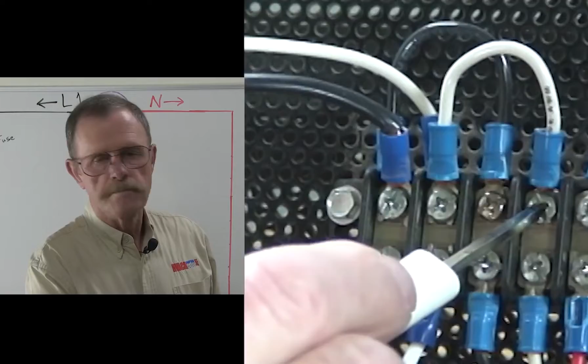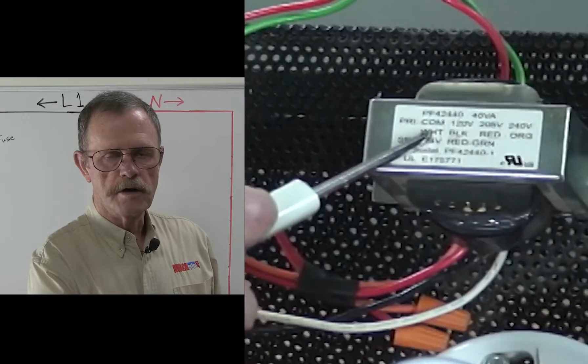I'm going to chase this one first. This neutral parallels over to here, and it goes to one side of the primary on the transformer, a 24 volt transformer, common is white, boom, it's hooked up. I'm going to draw that because I got to a load. I'll draw it down here because that's usually where you see transformers. So there's the 24 volt transformer, one side of it. I know where it goes, I've got it hooked up to neutral.